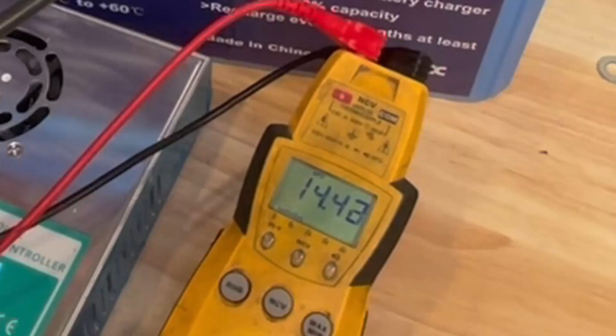And it looks like we're doing it again. Let me get my multimeter out here. Yep. So we're hitting that. So we're at 14.4. And then watch, it'll creep up and then hit 17 volts. So that's not good. We don't want to be hitting high voltage cutoff. So I'd have to keep lowering this until it's not hitting high voltage cutoff. But we're gonna use it as is and see what kind of capacity we get.